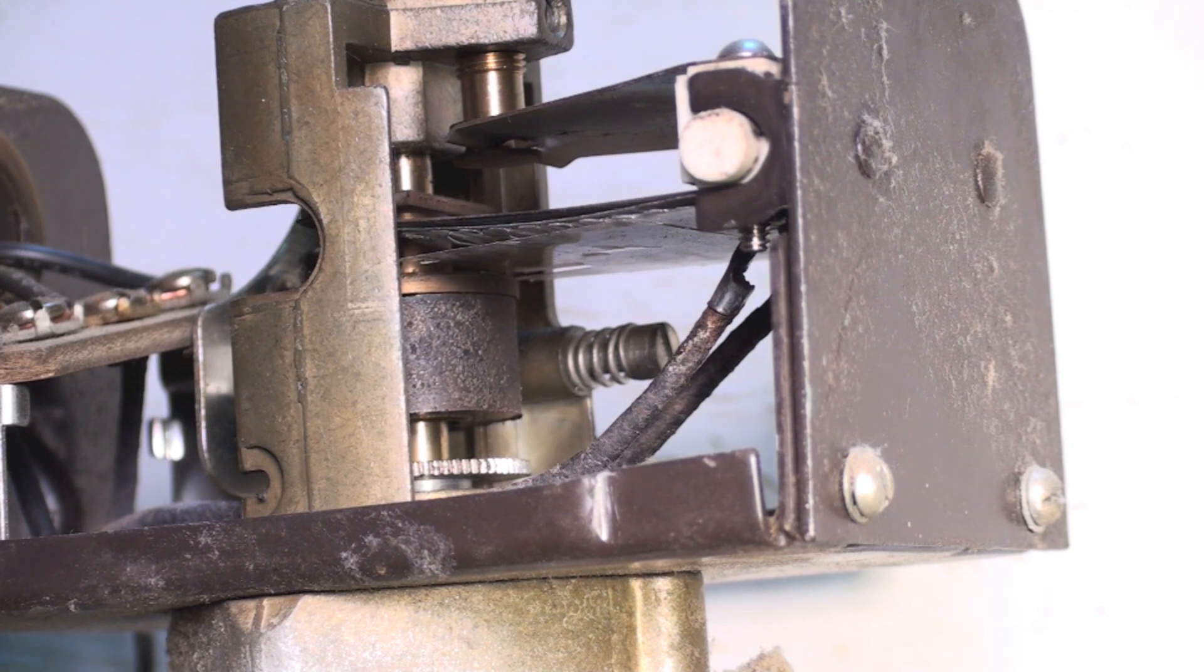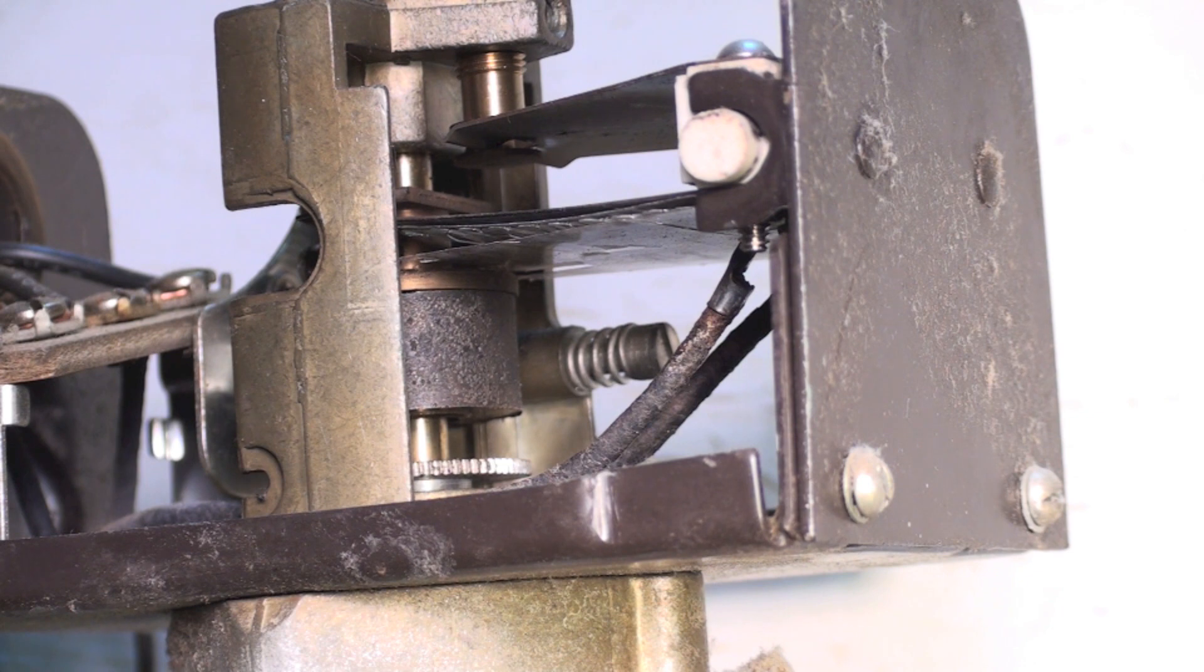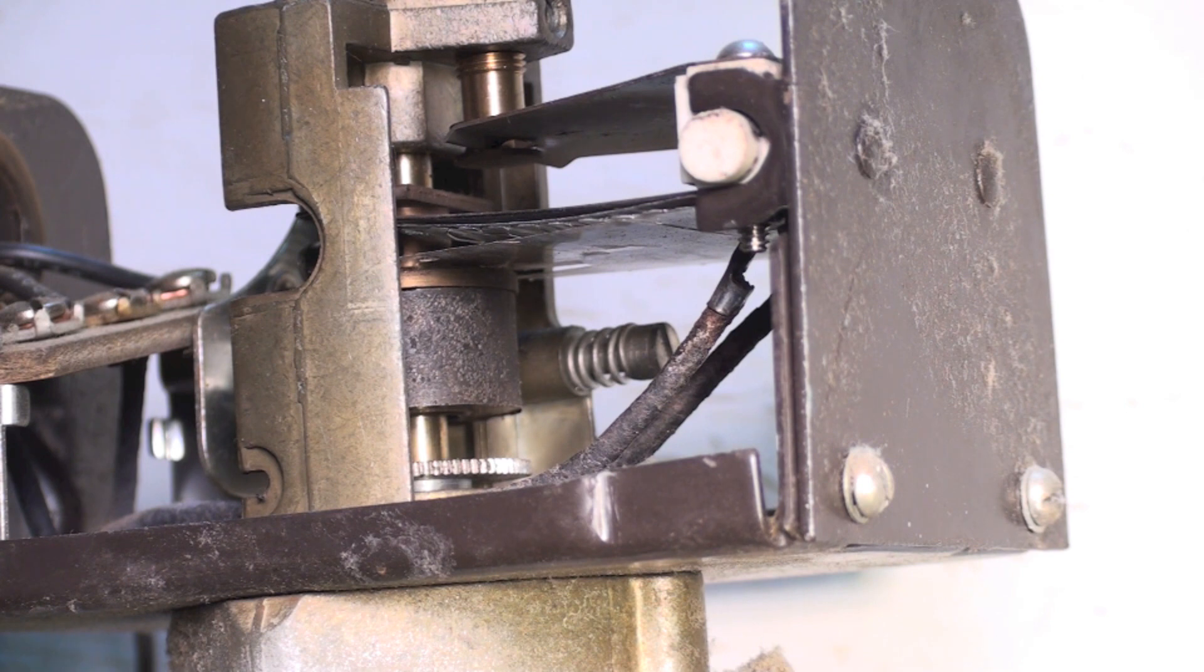Okay, now it's open completely. It took about 45 seconds for this to happen. So one of the things you should note when you're dealing with these things is if you turn on the thermostat, this thing is not going to take off for at least 30 seconds.